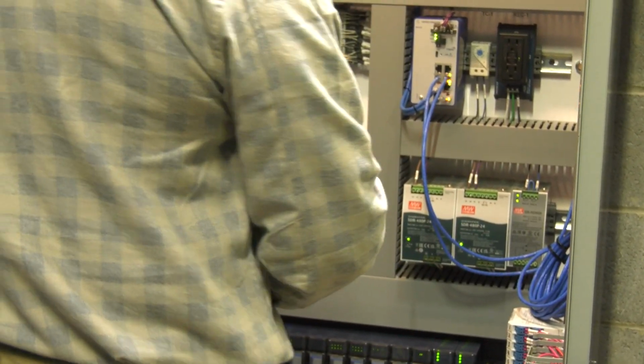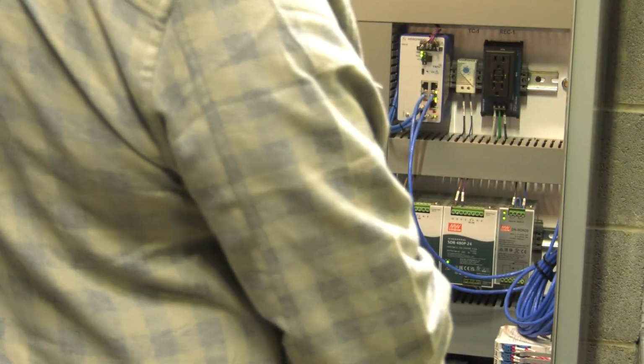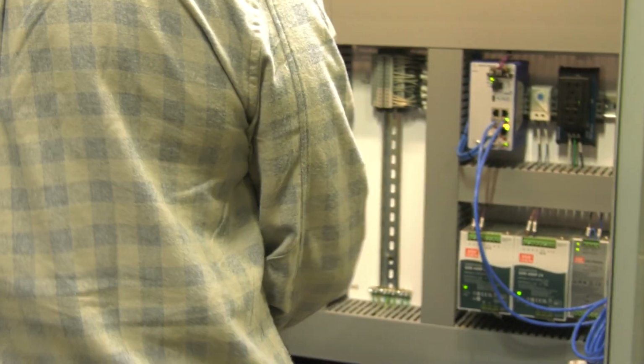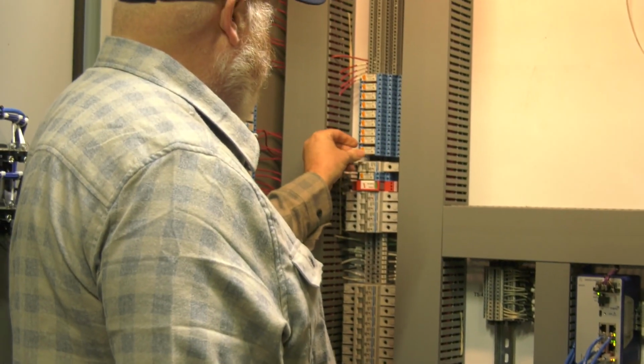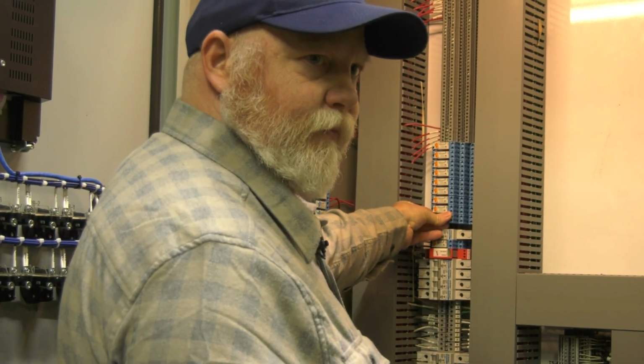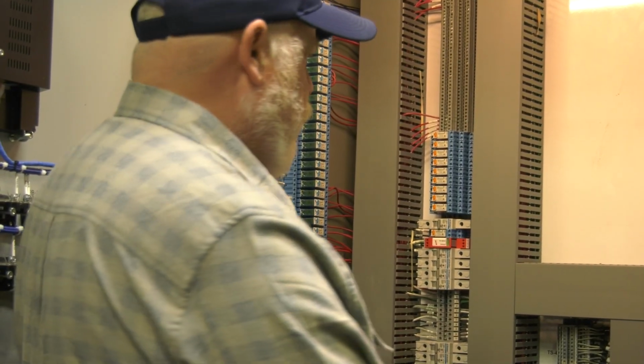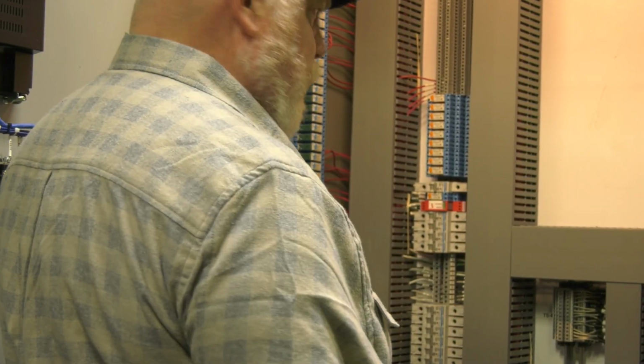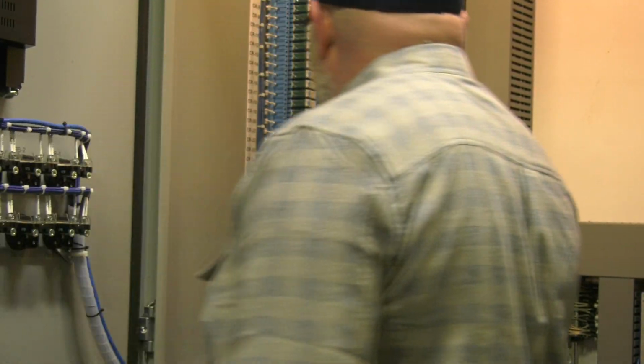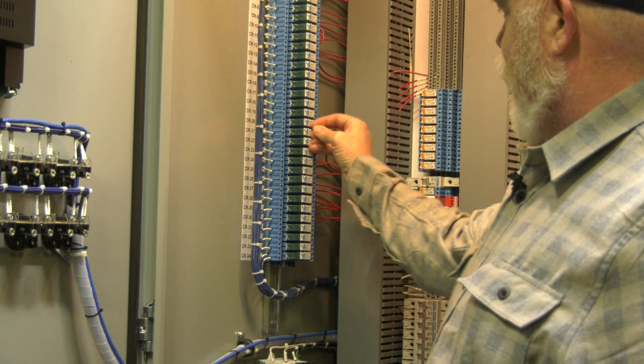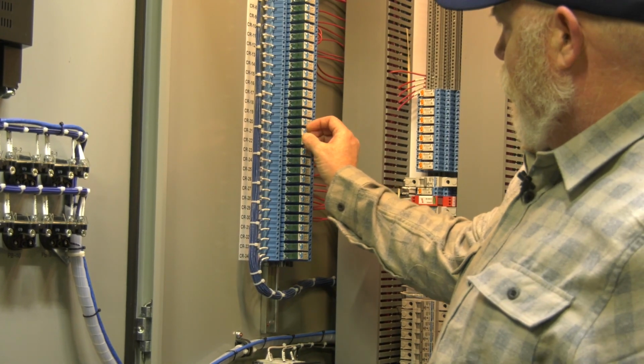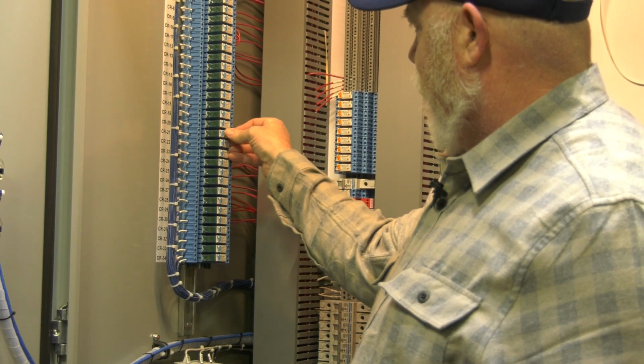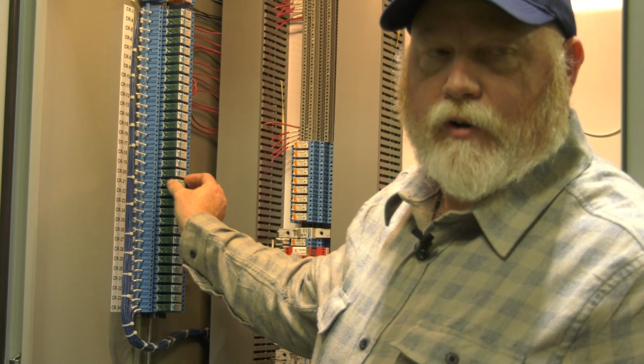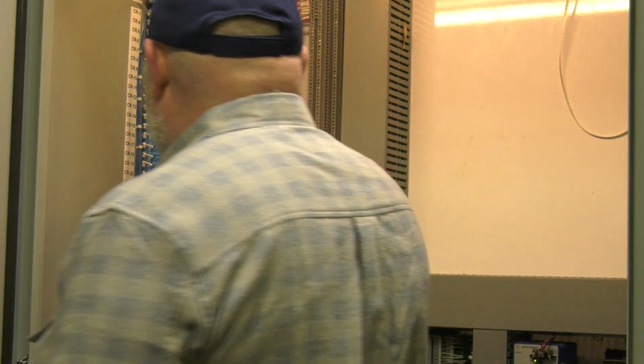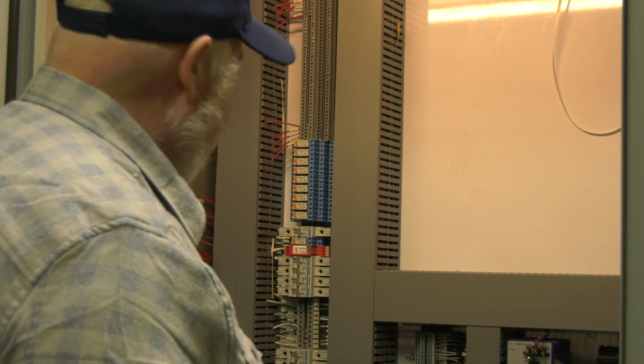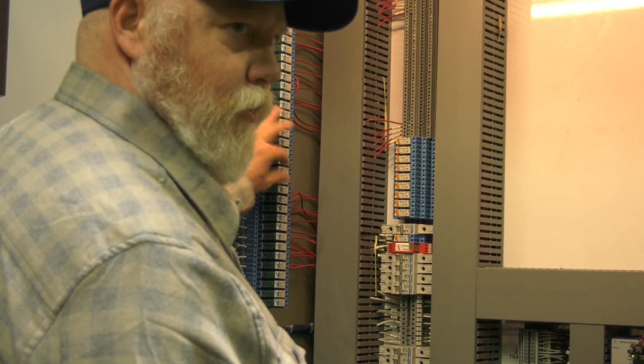Again, there's really no maintenance for those. Of course, here's your relays. And do you guys ever have to replace relays? Do you guys do that? Our electricians. Electricians do? Yeah. Okay. Well, they obviously just pop in and out. And one thing I was wanting to show you on these relays, there's a tab right there, and you can press that and that'll energize the relay. Well, there's a tab right here, and you can turn that flag right there, and it'll keep the relay on. So if your maintenance guy's trying to troubleshoot something, instead of standing here holding it or trying to force it in the PLC, you can force it by turning that flag.